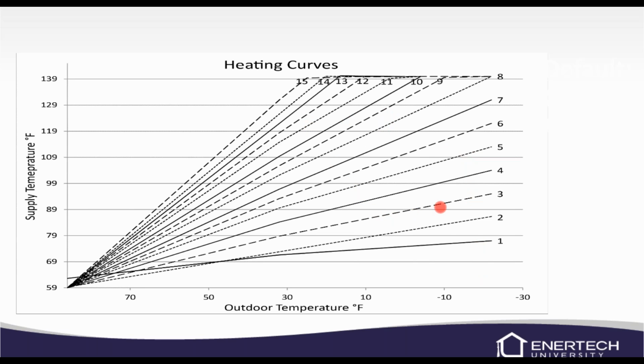You know, if we are on 3, when the outdoor temperature is 30, that water temperature is going to be about 79 degrees roughly. And then obviously as the temperature gets colder outside, we get into the 10 degree, then we're about, you know, 85 degrees and so on. So I know 3 usually works pretty well for here, maybe 4 or 5. The farther north you go, probably the higher curve you're going to need.